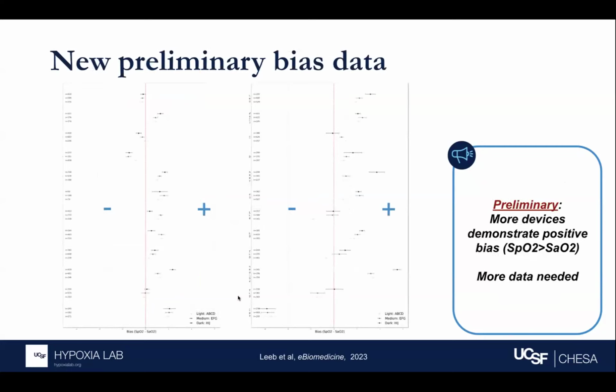In terms of preliminary bias analysis, when we run bias analysis of all the devices, on either side of the red line in the middle of each of these graphs, to the right is positive bias, the SpO2 from the pulse ox reading higher than the gold standard value. On the left is negative bias, under-reporting or reading lower. We're seeing most of them showing a positive bias. It is not as clearly showing the bias trend according to skin pigment group, but I am withholding assessment of this until we have more data, because we know we need more. But this will be forthcoming, hopefully pretty soon.